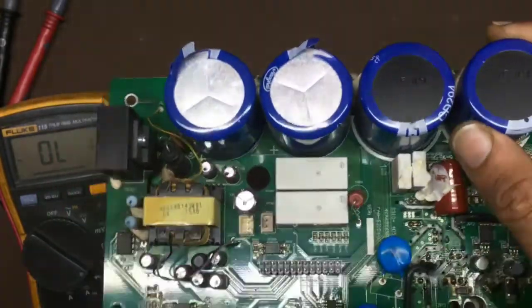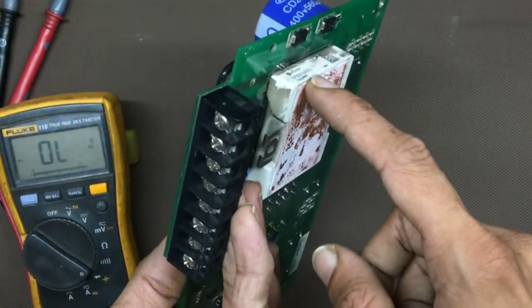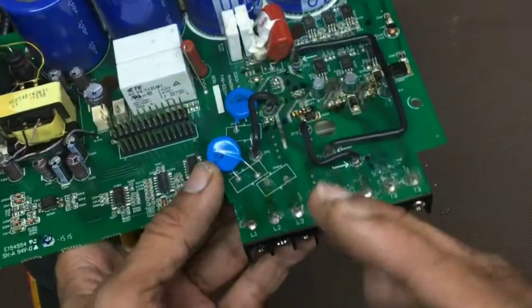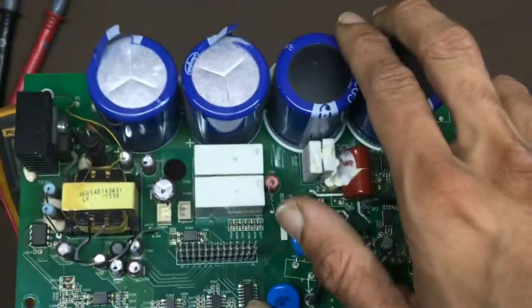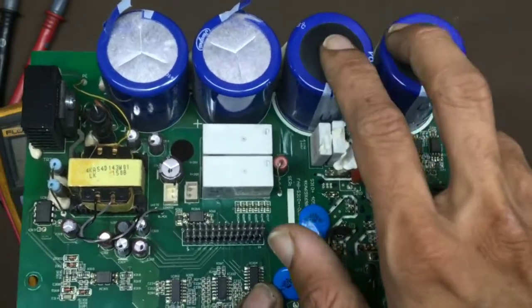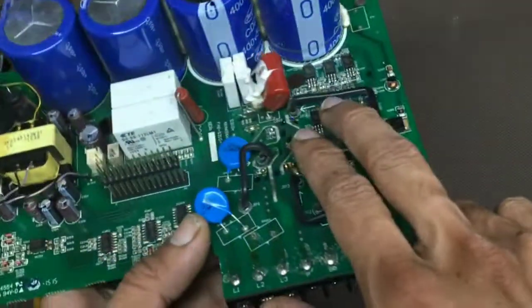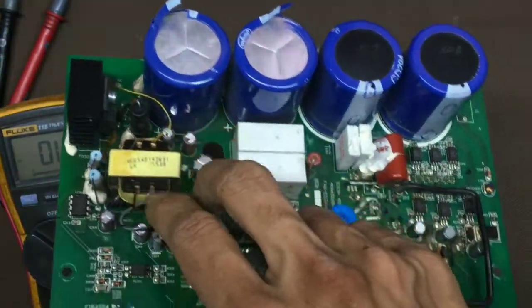The rectifier. This is the IGBT and rectifier built-in module, single module. So, the AC goes to the rectifier, then capacitor DC filters. Then, the IGBT inverts it to AC again and the UVW. And the SMPS section is switched on via the DC supply.